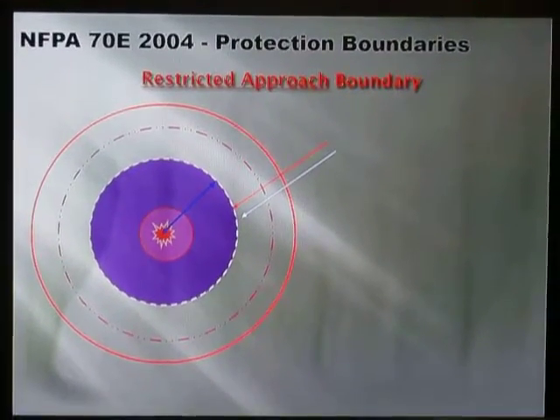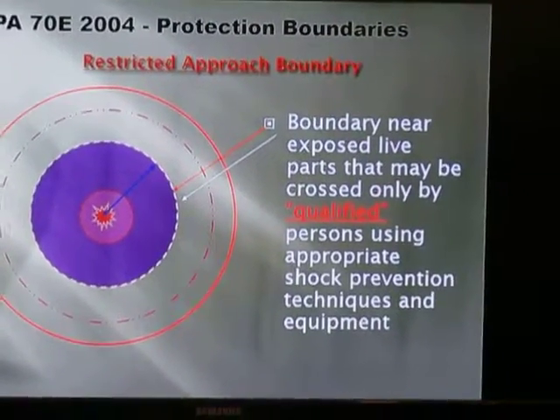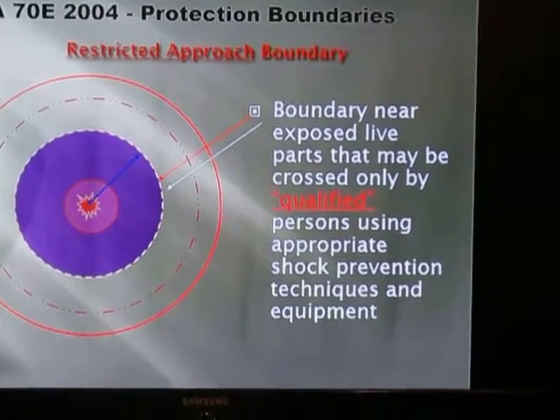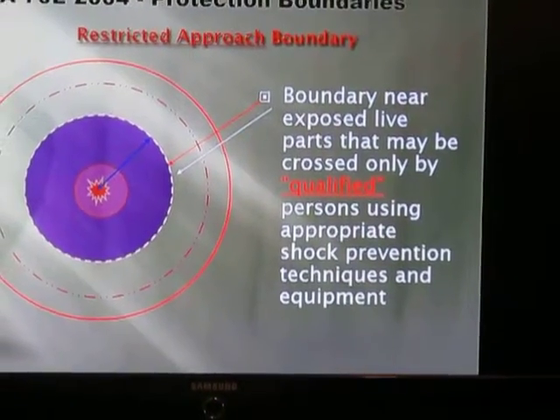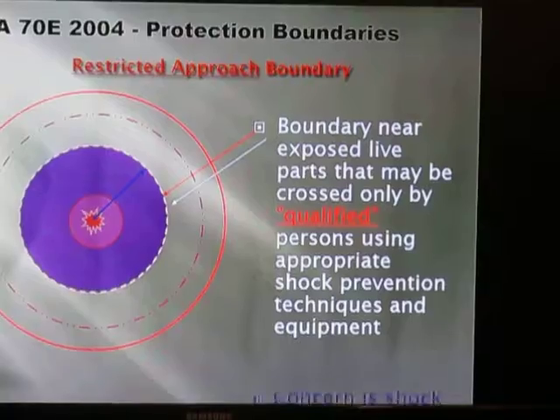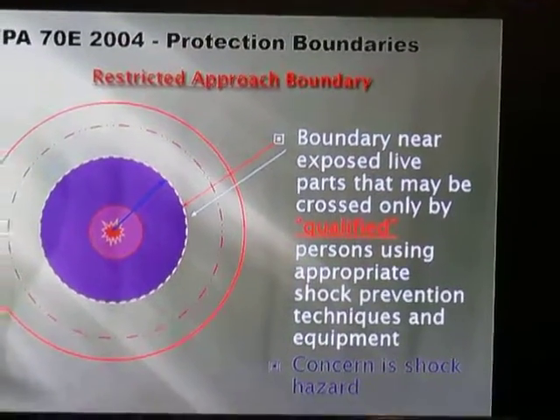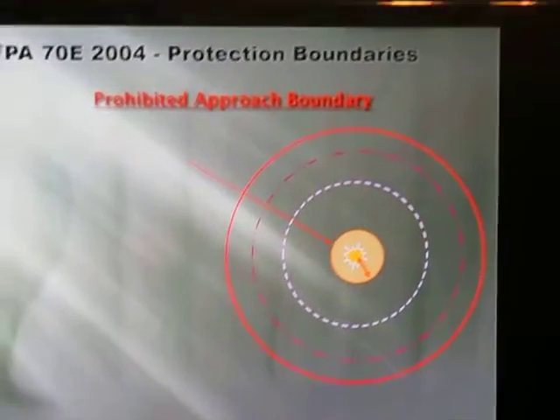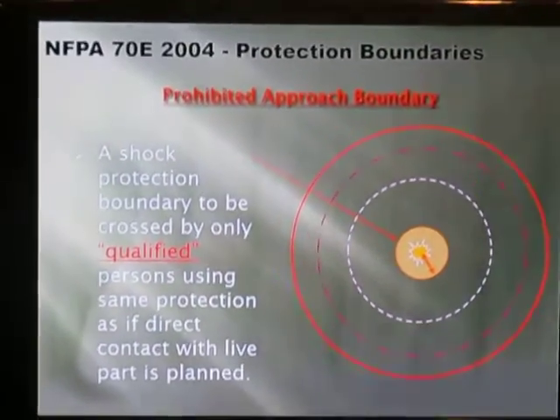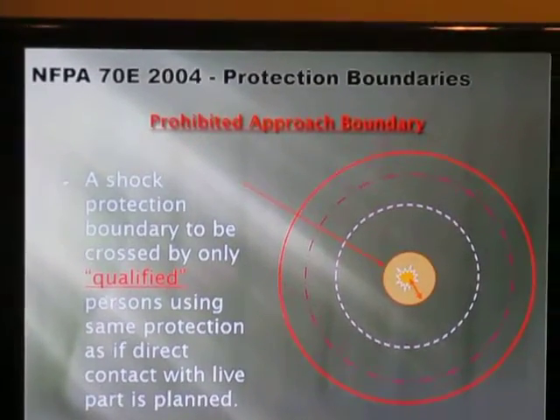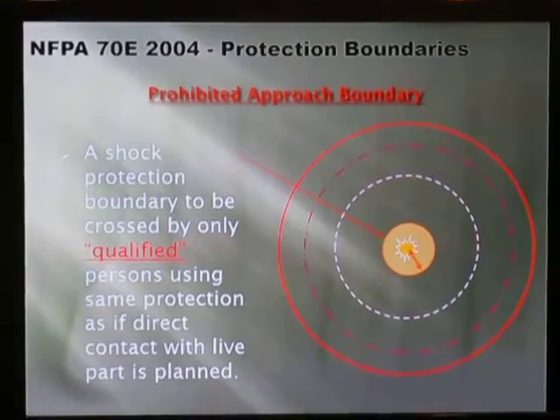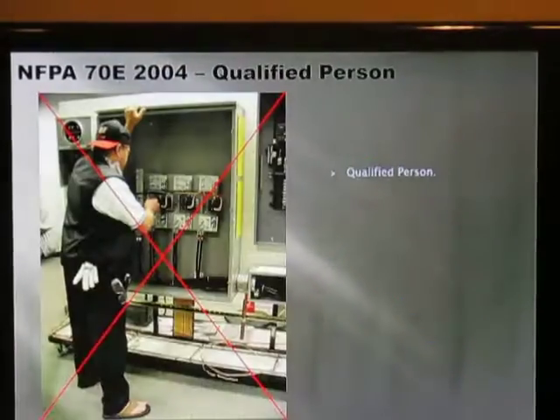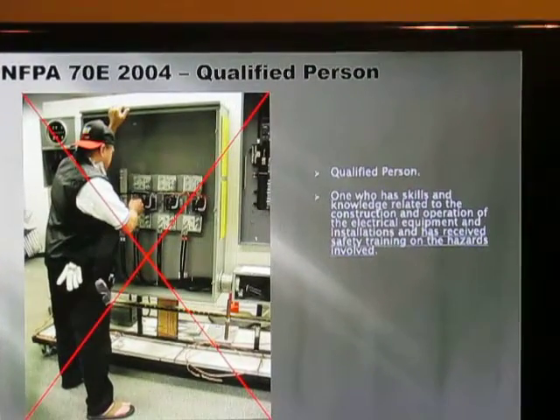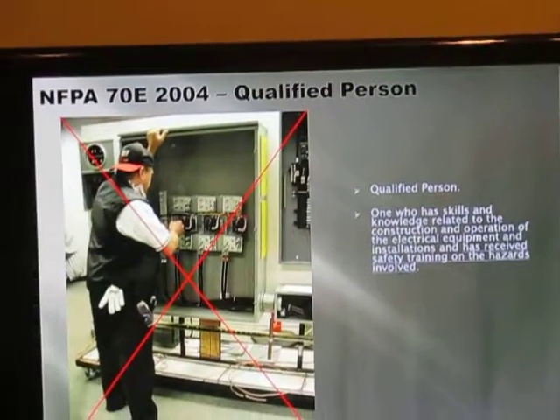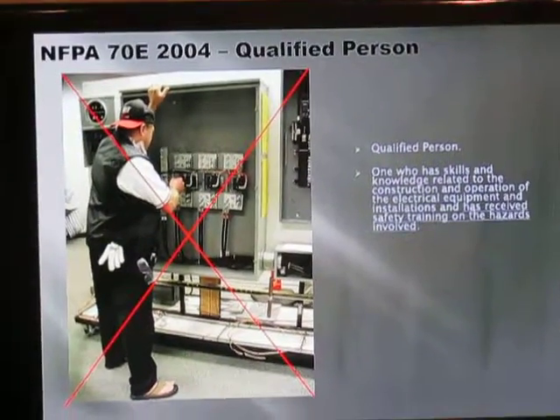This is the restricted approach boundary. The boundary near exposed live parts that may be crossed by only a qualified person using appropriate shock prevention techniques. It concerns the shock hazard. This is the prohibited approach. The shock protection boundary to be crossed only by qualified persons. You have to use that basically as if you're working on a live wire. And what is a qualified person? It is one who has been trained, who knows the hazards of the electrical.